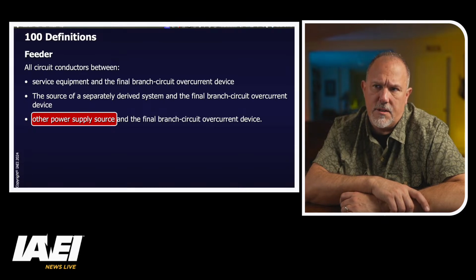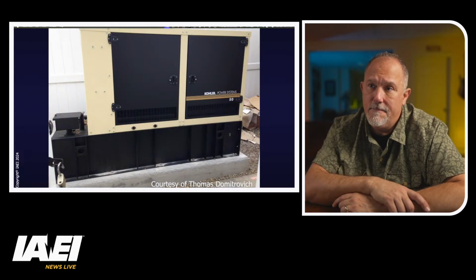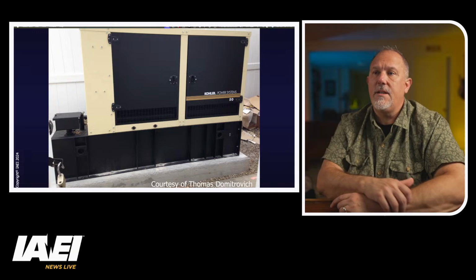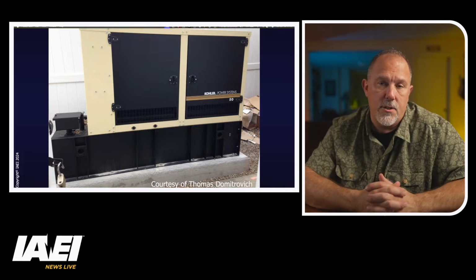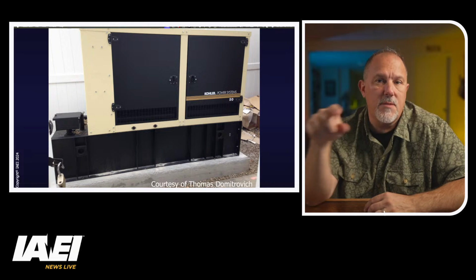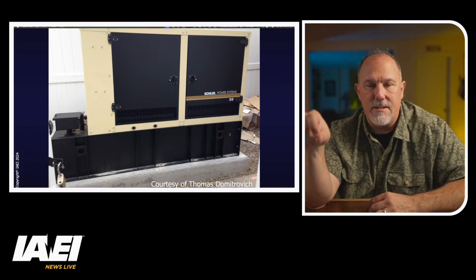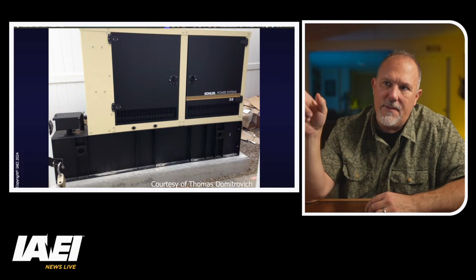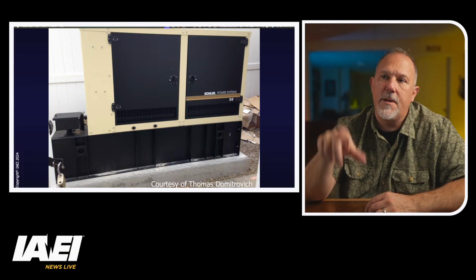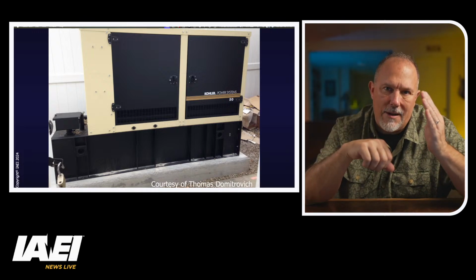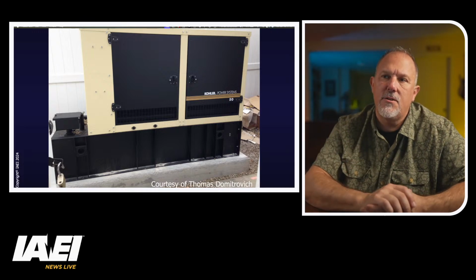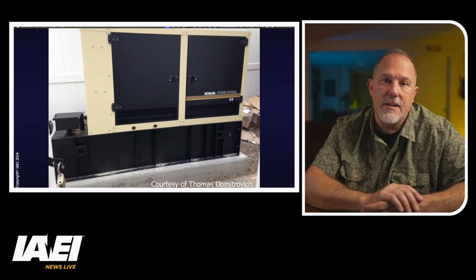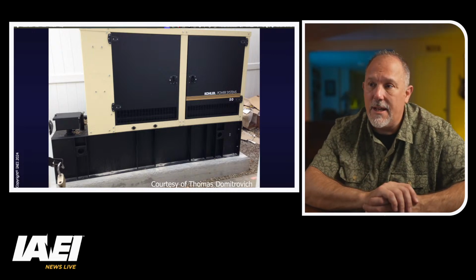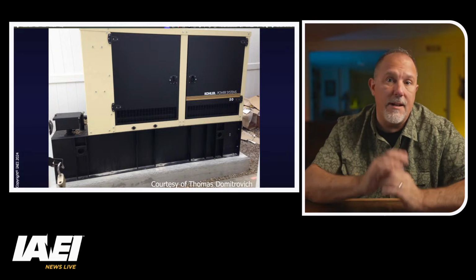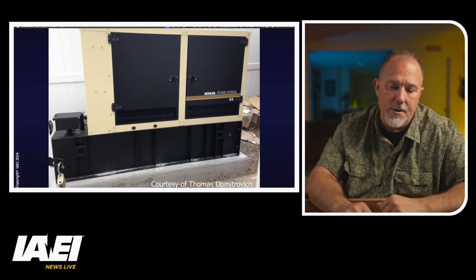Another power supply source and the final branch circuit overcurrent device. Well, what are other supply sources? It's not a defined term, but a generator would be an other supply source. A generator could be a separately derived source, but it depends upon how I bond and ground it. If I put a ground rod at this piece of equipment, and I bonded the grounded conductor with the equipment grounding conductors and the grounding electrode conductor, and I established a separately derived system, then yes, that could be a separately derived system. But typically this is a non-separately derived system.